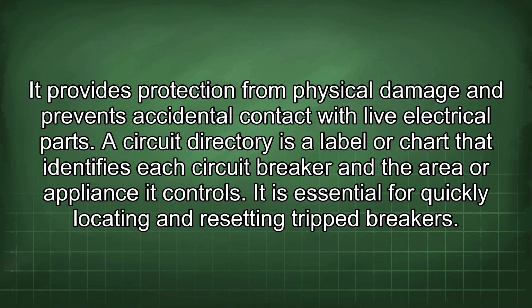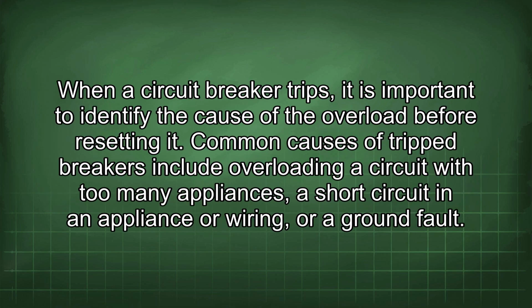A circuit directory is a label or chart that identifies each circuit breaker and the area or appliance it controls. It is essential for quickly locating and resetting tripped breakers. When a circuit breaker trips, it is important to identify the cause of the overload before resetting it. Common causes of tripped breakers include overloading a circuit with too many appliances, a short circuit in an appliance or wiring, or a ground fault.